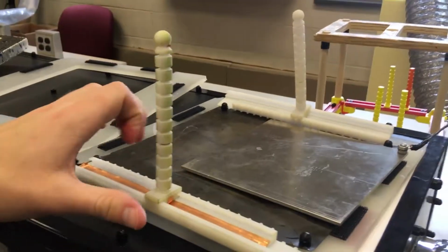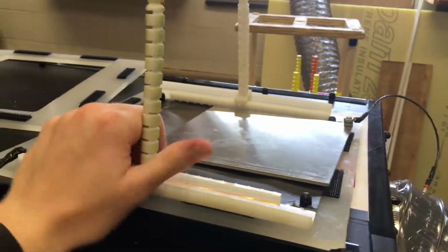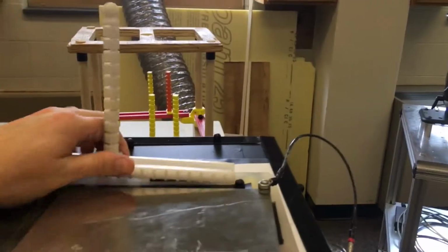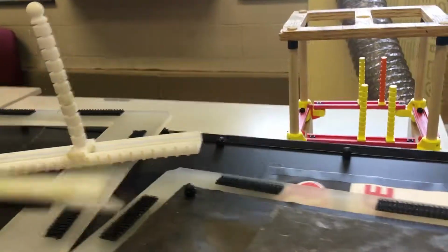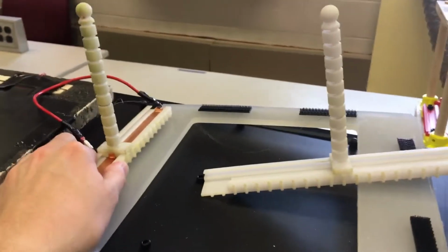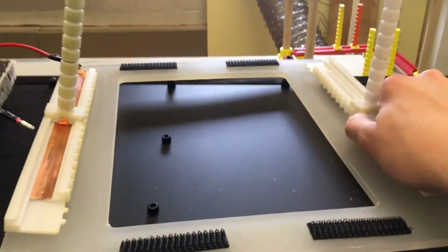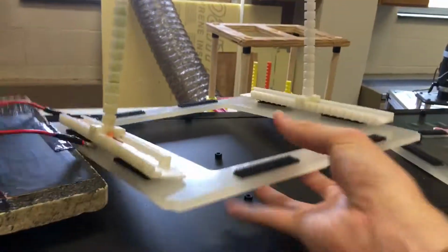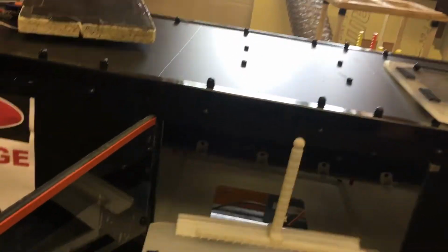To prepare for a heat transfer test, you would take the slide out of the chamber for the water loss test, and then you can take off these rails due to Velcro, and you can switch it over to the hot plate test, which is this slide here. So you can take that and then suspend the electrode across, just snap those in. Once that is in place, you can take out the spacer for the water loss test, and then you can take this new slide and put it in the front door of the testing chamber.